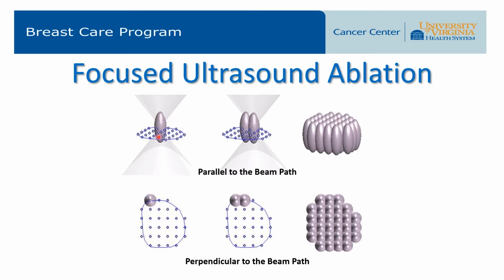Again, here are those sonication zones depicted from the side. Right here is cigar-shaped, and here is that same sonication zone depicted from above, which would look like a circle. We create a treatment plan viewed from above here and viewed from the side here, and then we sonicate, producing a sonication zone. We then move the device to the next treatment target, sonicate again, producing another sonication zone, again depicted from the side here and from above here, and then we cobble together all of these treatments so that at the completion of the treatment, the entire volume within the treatment plan is sonicated and treated.